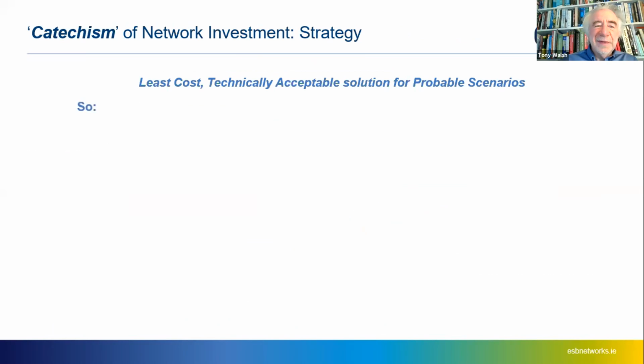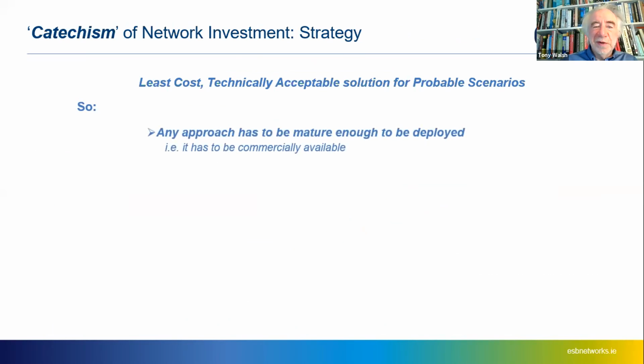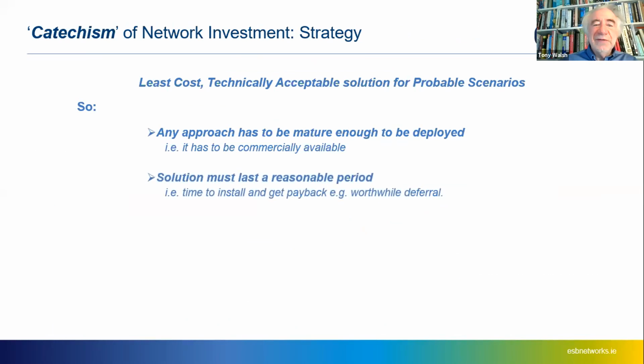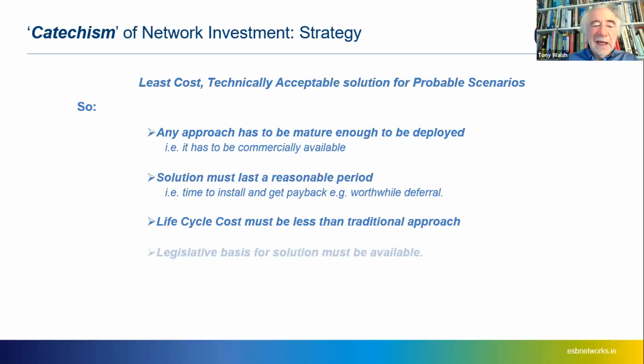In essence, this means any approach has to be mature enough to be deployed, so it has to be commercially available. The solution must give a payback in a reasonable period - you don't want to put in something that takes too long to pay back. If it gives a deferral on the network for 5 years and pays itself back in 4 years, great. If it has a 5-year payback but you only get 1 year's deferral before you need to upgrade the network, it's useless. If it's a new type of solution, its life cycle cost must be less than the traditional solution, and there must be a legislative basis for the solution to be available.